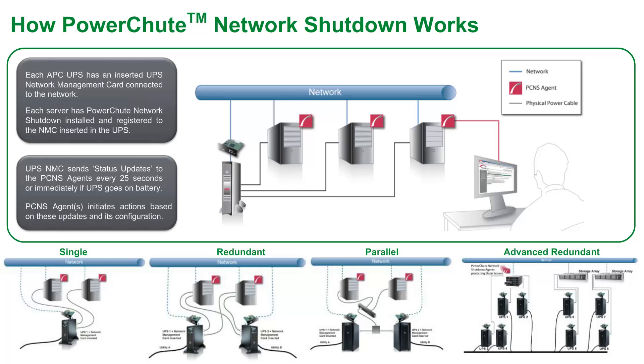PowerChute Network Shutdown recognizes that the UPSs are set up in a parallel configuration and will monitor the changing load on the UPSs to manage how UPS events are aggregated, depending on the level of redundancy in the system at any given time. The advanced UPS configuration enables a single PowerChute Network Shutdown agent to monitor multiple UPS setups and initiate graceful shutdown based on different redundancy levels. Each UPS setup can be a single UPS or a UPS group of two or more UPSs.